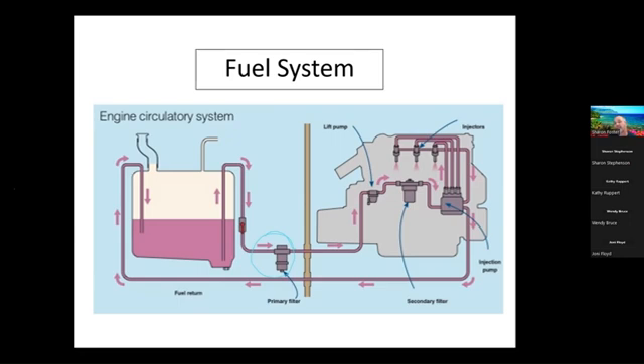That's where the confusion is, because they say, well, if it's provided by the engine, it should be primary, but that's your secondary. All right. From the secondary filter, it's going to go to your fuel injection pump. And from the fuel injection pump, that's where your throttle linkage is hooked to. That's where your fuel stop is connected to. And then from there, it's going to go up to each individual injector.